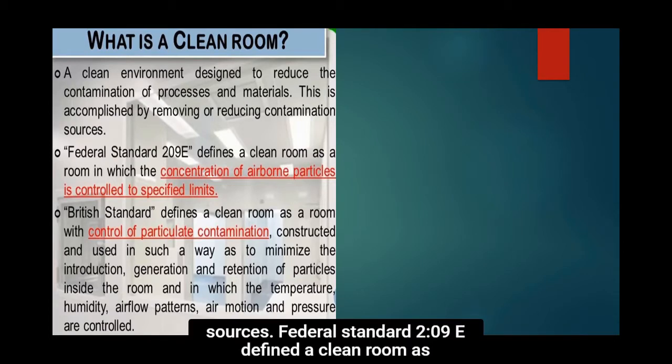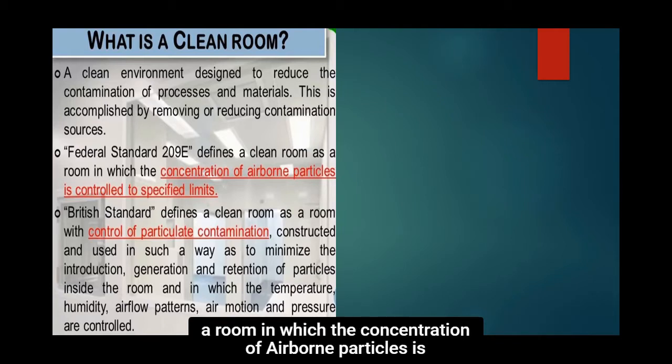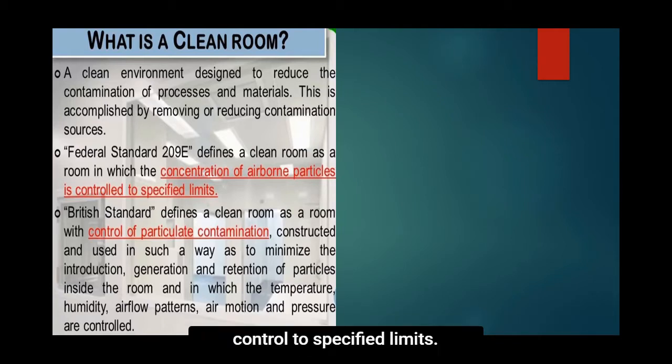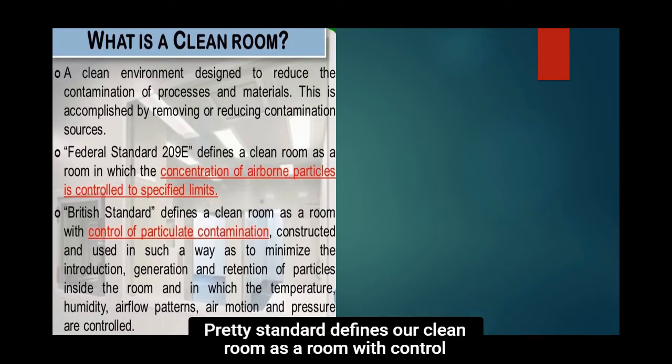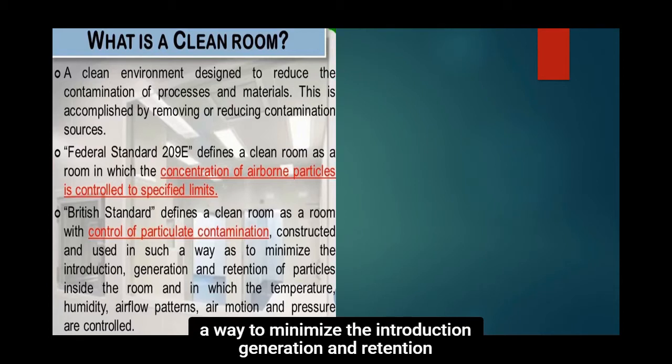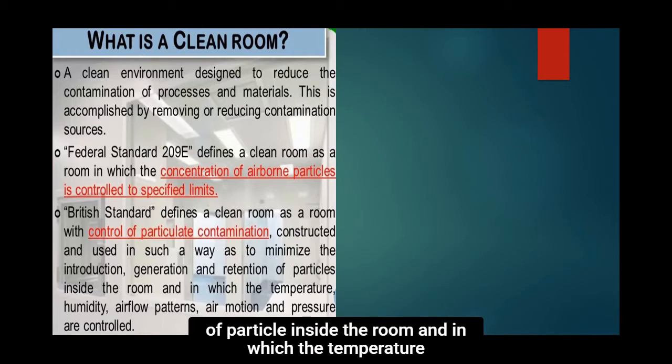Federal Standard 209E defines a clean room as a room in which the concentration of airborne particles is controlled to specified limits. British Standard defines a clean room as a room with control of particulate contamination, constructed and used in such a way as to minimize the introduction, generation and retention of particles inside the room, and in which the temperature, humidity, airflow pattern, air motion and pressure are controlled.